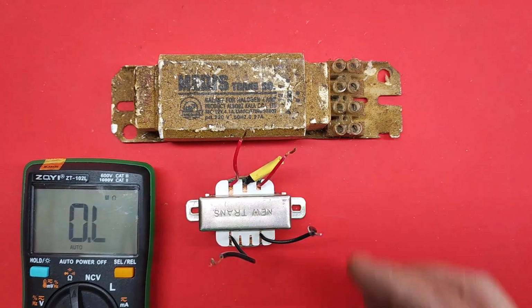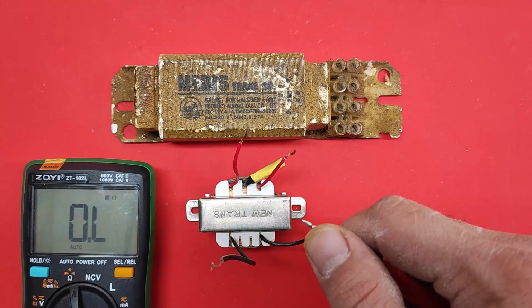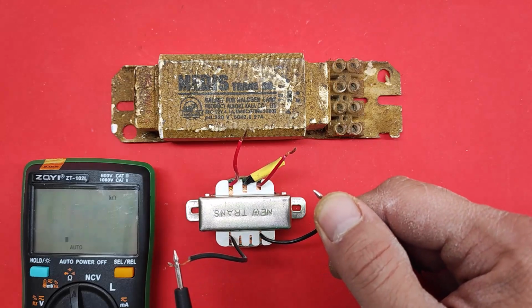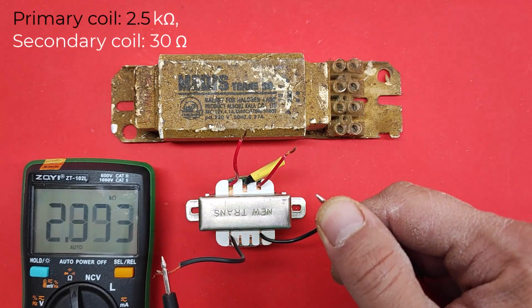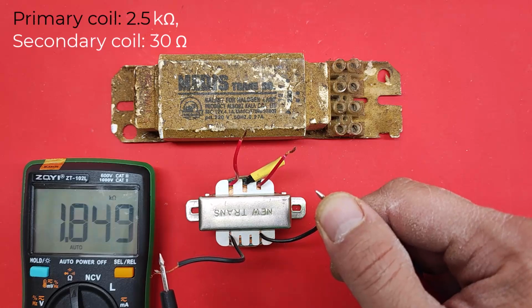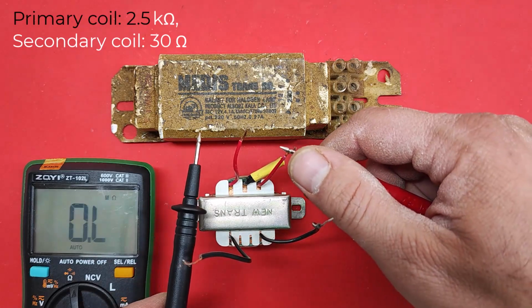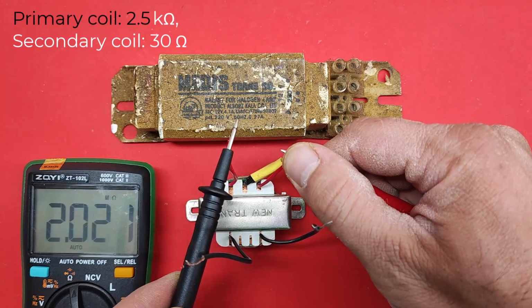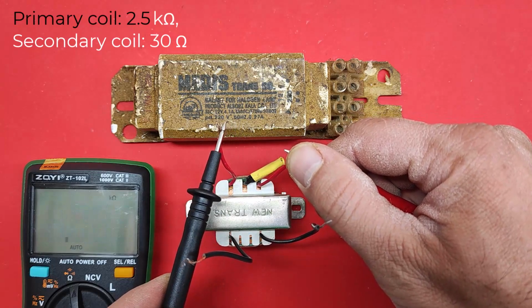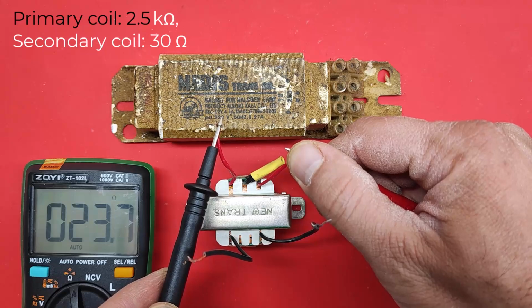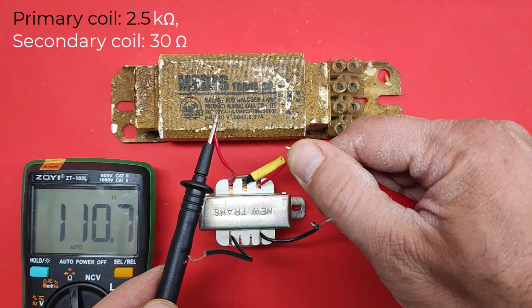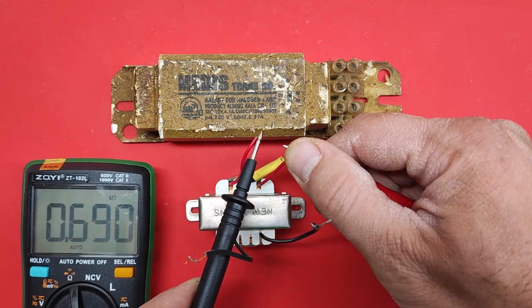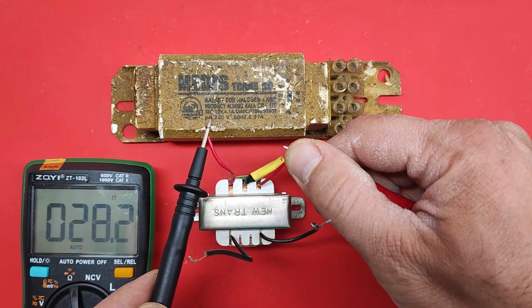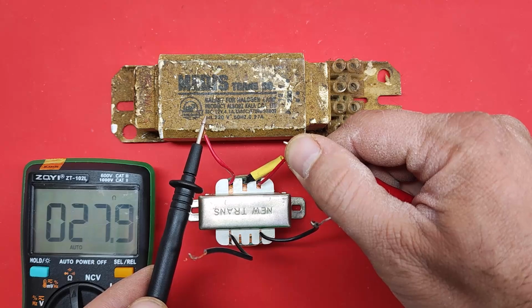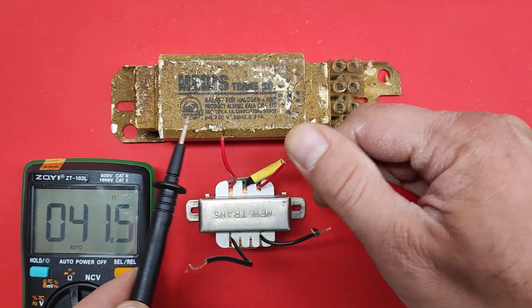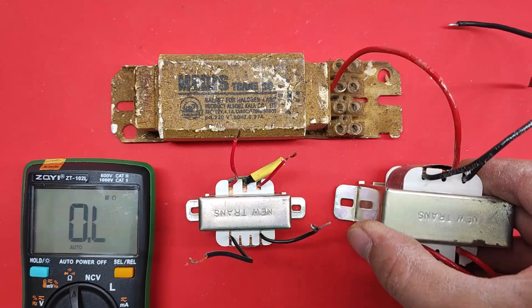Now moving to the first standard power transformer. It has a 220-volt input and a 24-volt center-tapped output. The output current is around 1 ampere. The two outer terminals give 24 volts and the center tap provides 12 volts. The primary winding resistance is about 2.5 kiloohms, which is relatively high compared to the secondary. The secondary winding resistance for the 24-volt output is around 30 ohms.